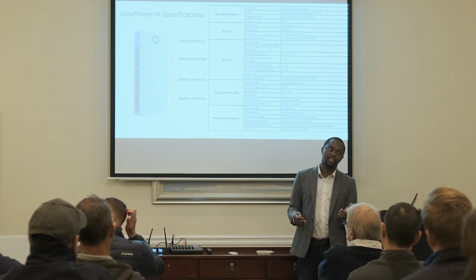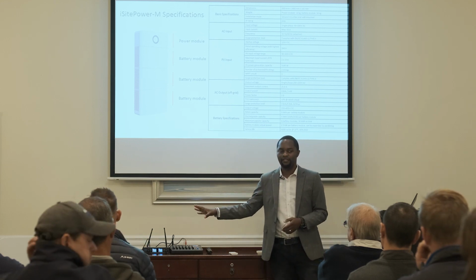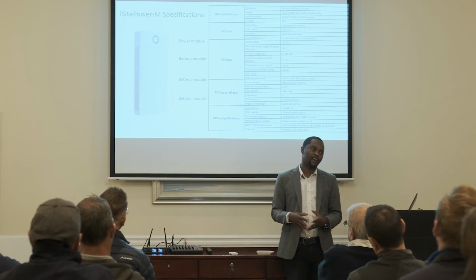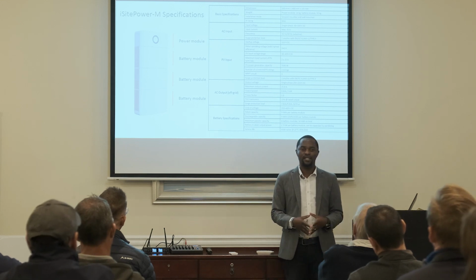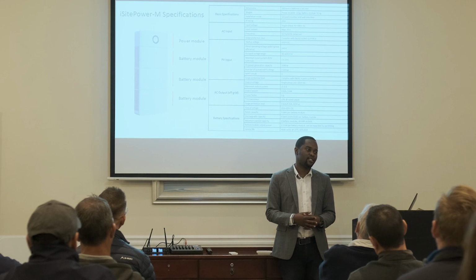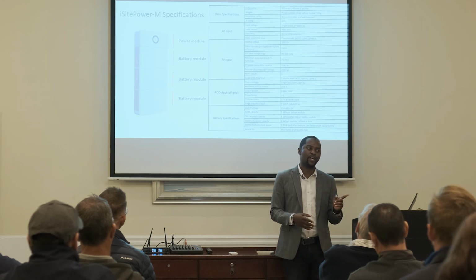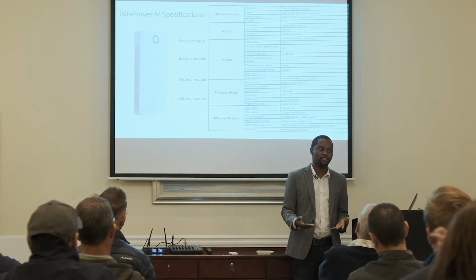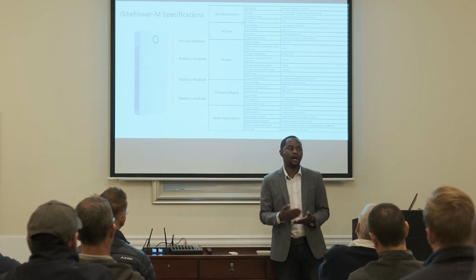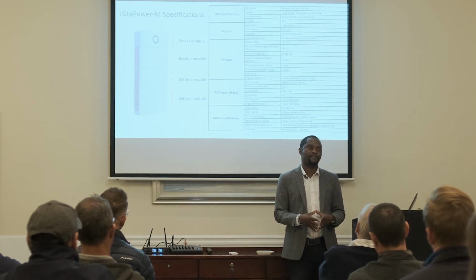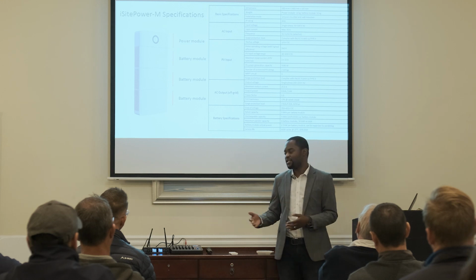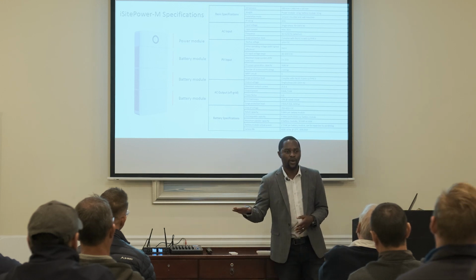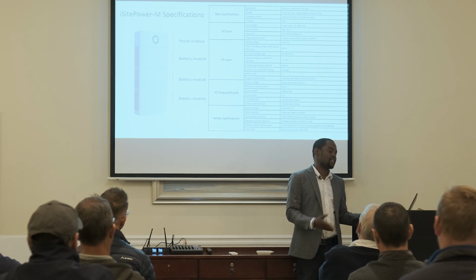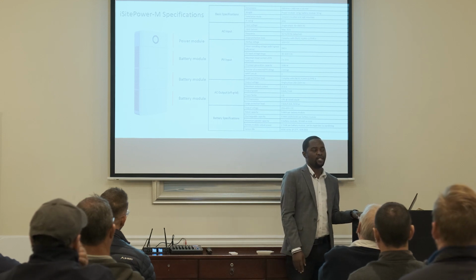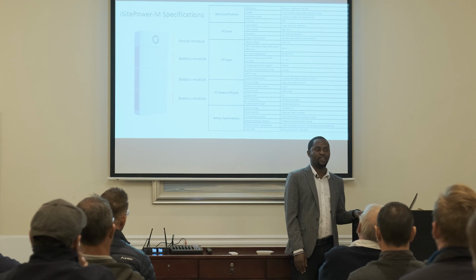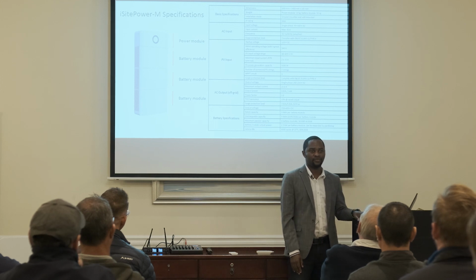If you've got 1 battery, though you've got a 5 kilowatt inverter, you can only take 2.5 kilowatt. So you install it on a system, then the client calls you saying the system is tripping at 3 kilowatt, but they've got a 5 kilowatt inverter. It's because your battery can only allow you to discharge up to 2.5 kilowatt. But we've done tests, it's actually 3 kilowatt. Huawei, just to be on the safer side, classified it as 2.5 kilowatt. But you can take my word, it won't trip before 3 kilowatt. All right.